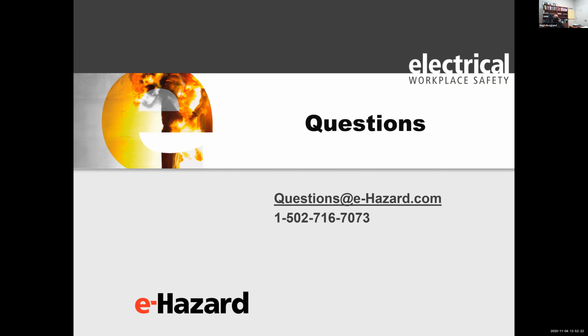No, just that if it's exposed to arc flash, it needs to meet ASTM F887. The 887 is not mandatory, but OSHA by law has required a 40 cal arc test, which is literally what we do in 887. So anyone covered by 1910-269 would have to use an 887 harness, which has an arc flash test at 40 calories, and then it's dropped afterwards to make sure it still works. Most of those will be flame resistant or really, really thick nylon, but they have to have specific keepers to make sure the keeper doesn't ignite and catch the nylon on fire. So most people are going toward a Nomex or Kevlar type vest, or some of the really heavy nylons specially made for arc flash.